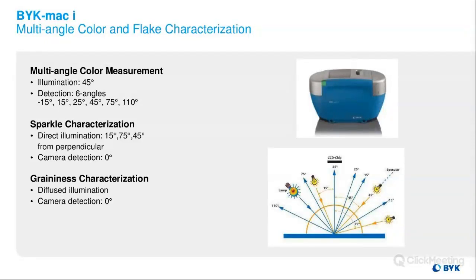Question from Ashley here. Will the multi-angle measure solid/standard colors accurately, or should it purely be used for the added effect paints? It can, yeah. The illumination angle here with the multi-angle instrument is at 45 degrees, same as our 45-0 instrument. It's a little weird that the convention is different for multi-angle color than it is for solid color.